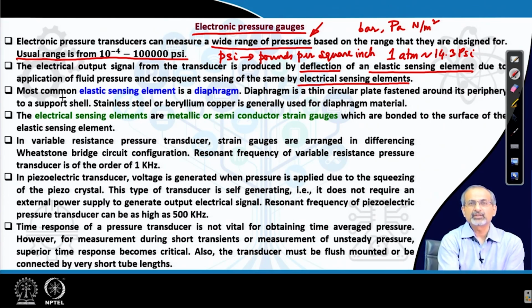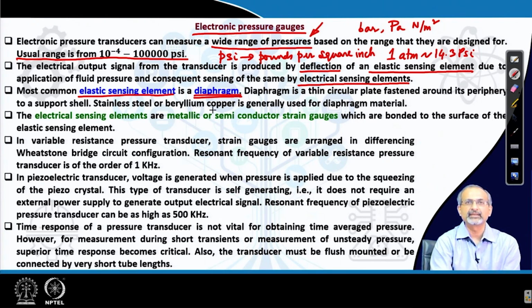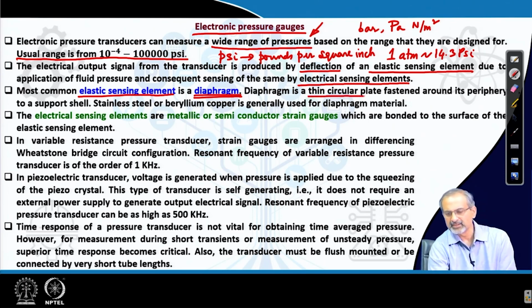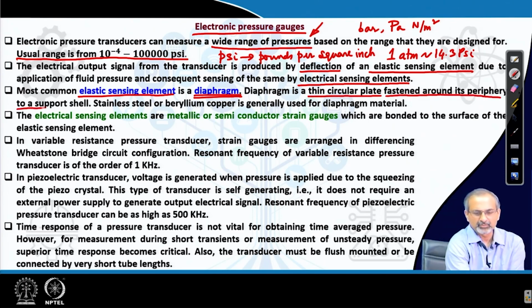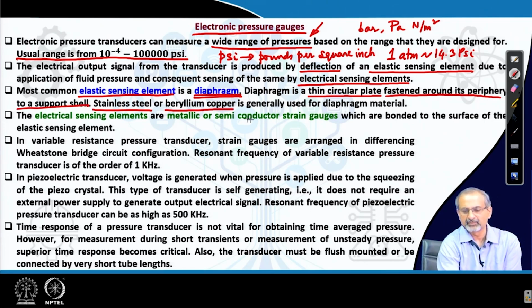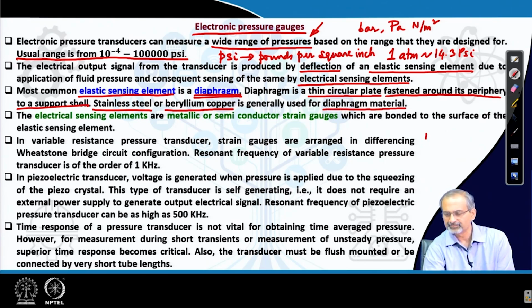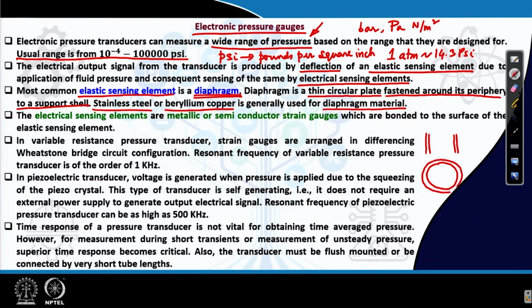So, let us see configurationally what is the difference between what we have seen in a balance, where we had used a cantilever beam like setup which we call the sting balance, and what we are calling a pressure transducer. In the pressure transducers, most often the elastic sensing element is a diaphragm. We are no longer talking about a sting or a cantilever beam, but a very thin diaphragm which can respond to pressure changes. It is usually a thin circular plate fastened around its periphery to a support shell. Usually stainless steel or beryllium copper is used for the diaphragm material. So, what are we looking at? In side view, it will look somewhat like this. So, you have a shell like we said. In top view, it is like this, right, and on top you have a very thin diaphragm.